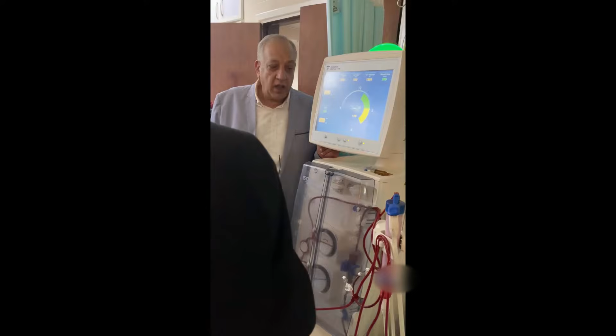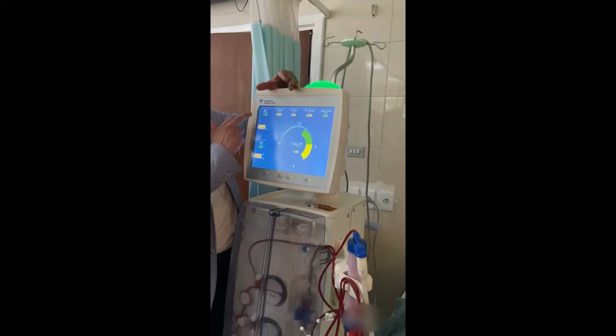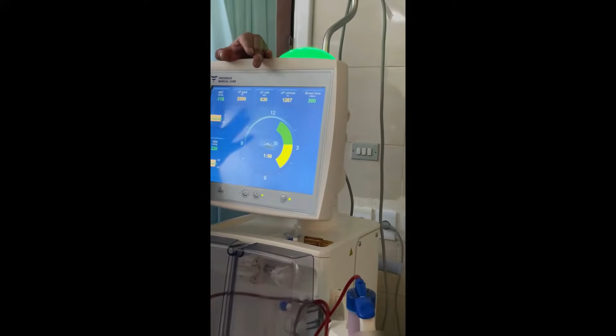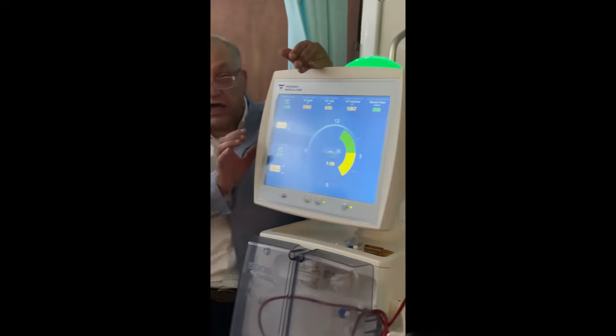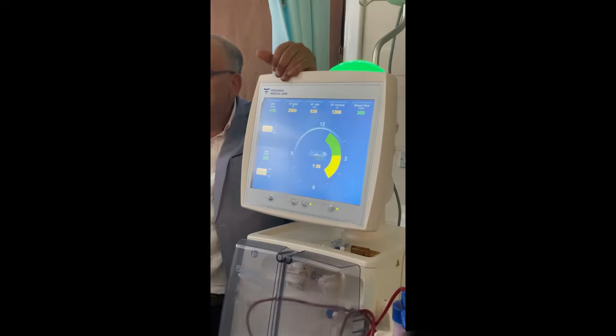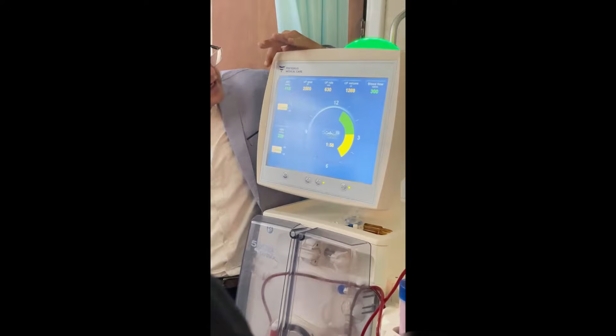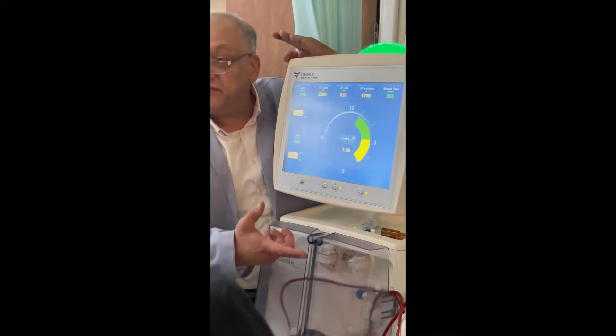Let us go to the parameters, and if you focus here, you can find one parameter which is very important: arterial pressure. Arterial pressure here is 115 on a blood flow of 300. Good. This is a negative pressure, not a positive pressure like in venous, because the negative pressure here is pre-pump, so it calculates the efficiency of the arteriovenous system.